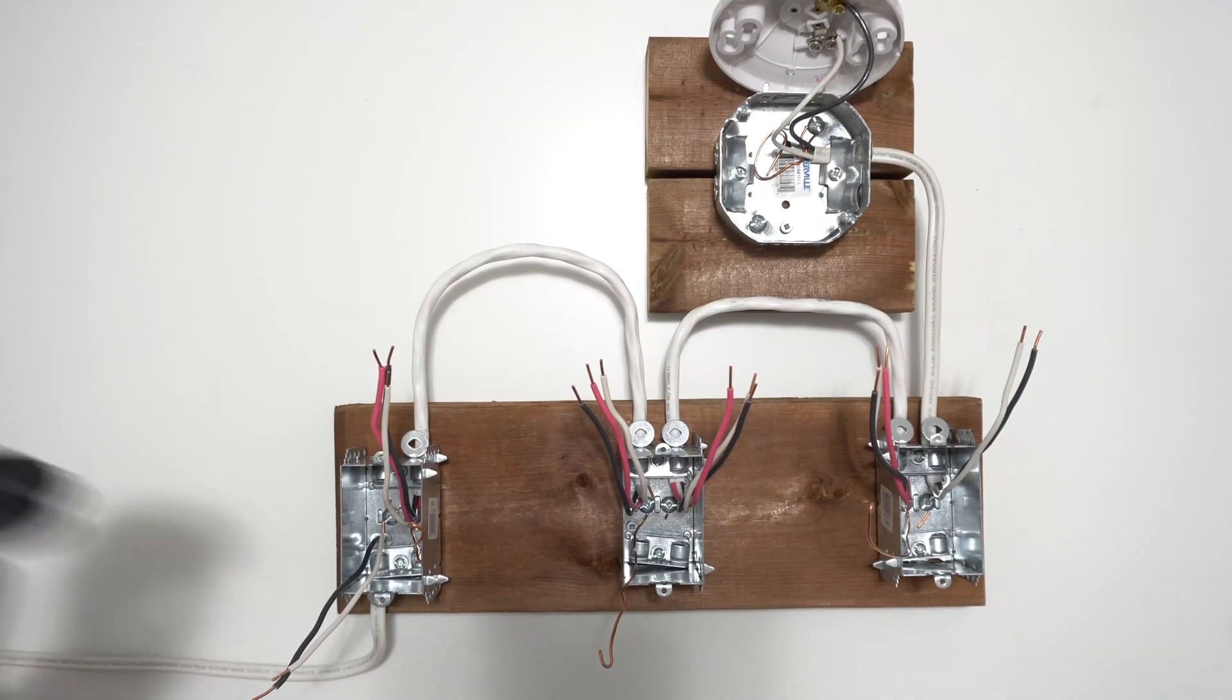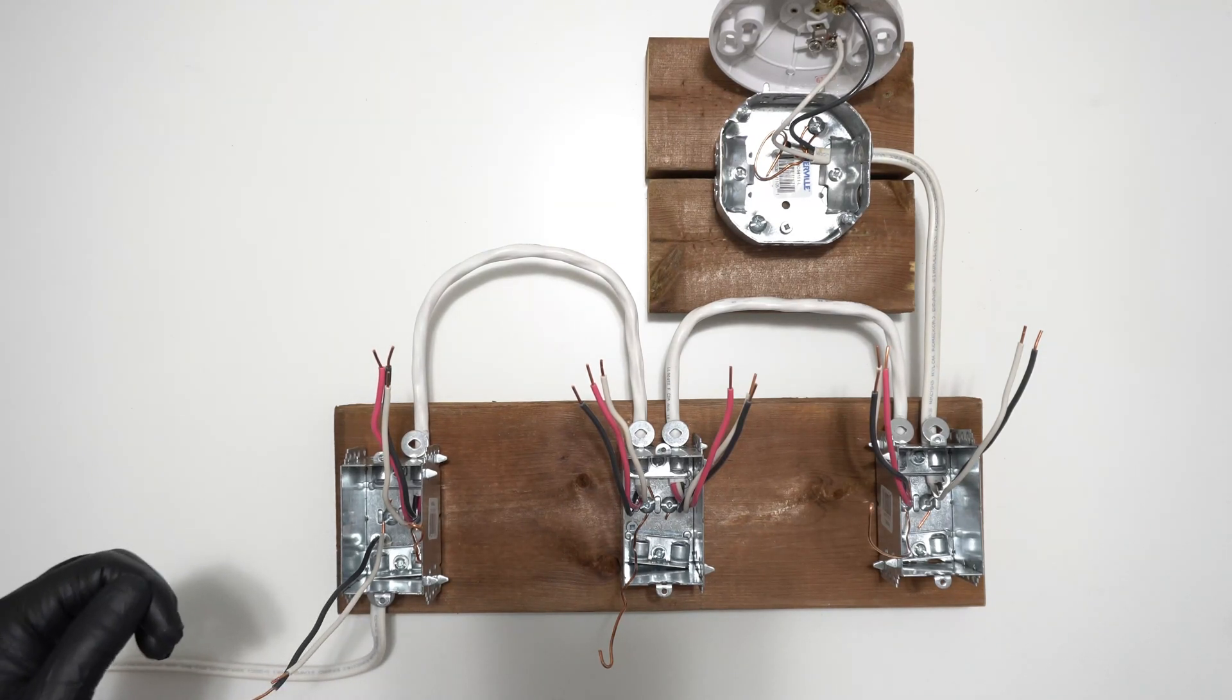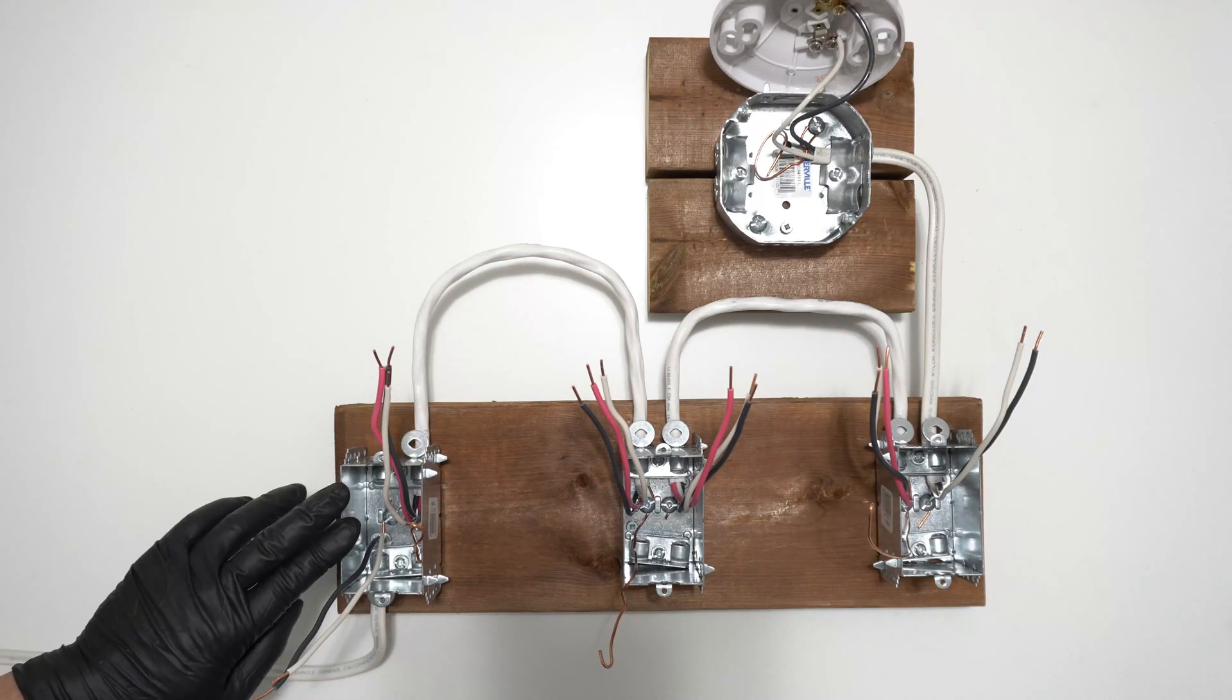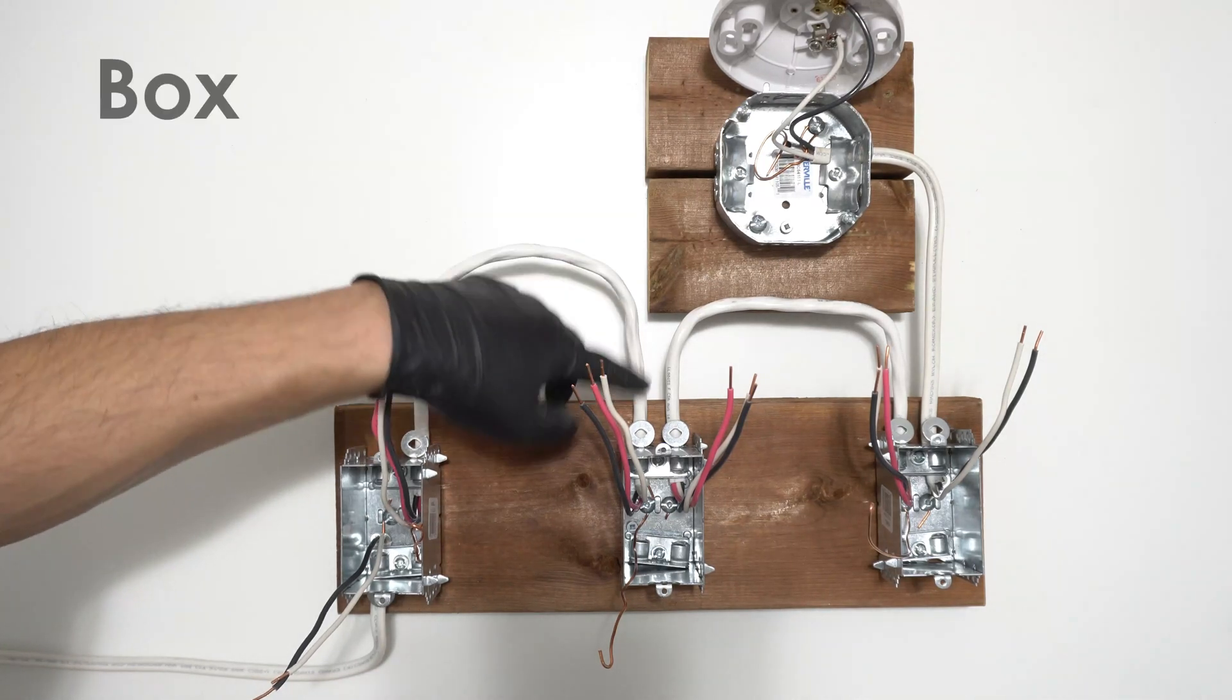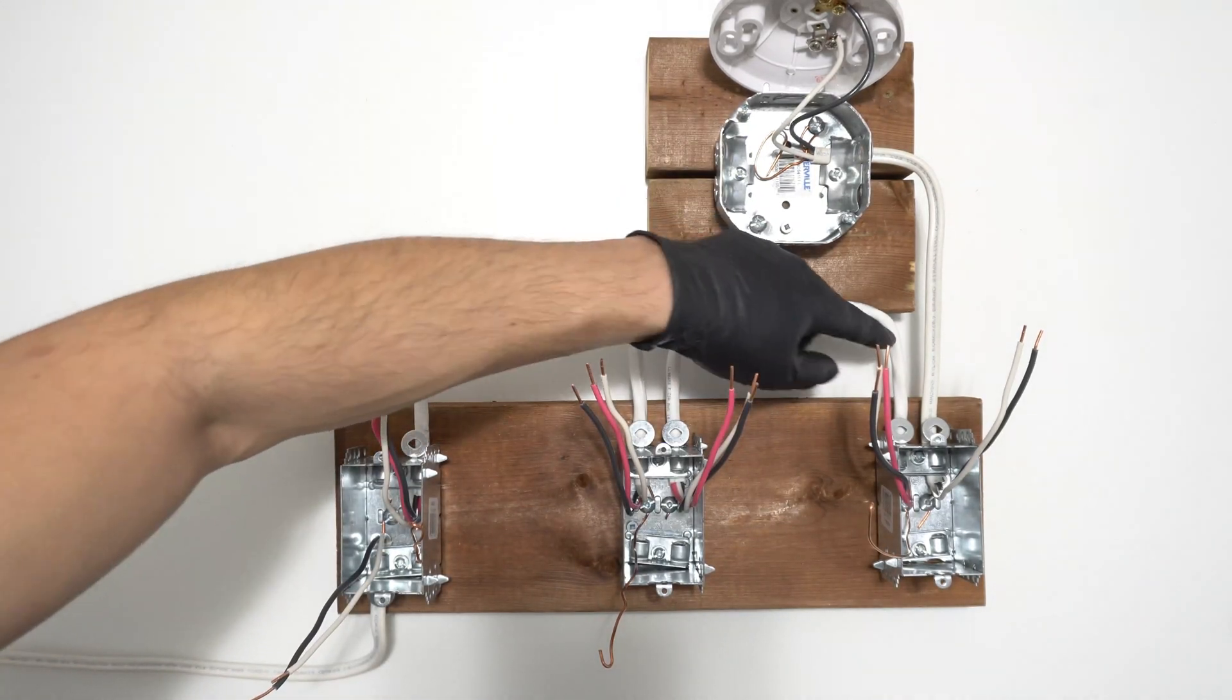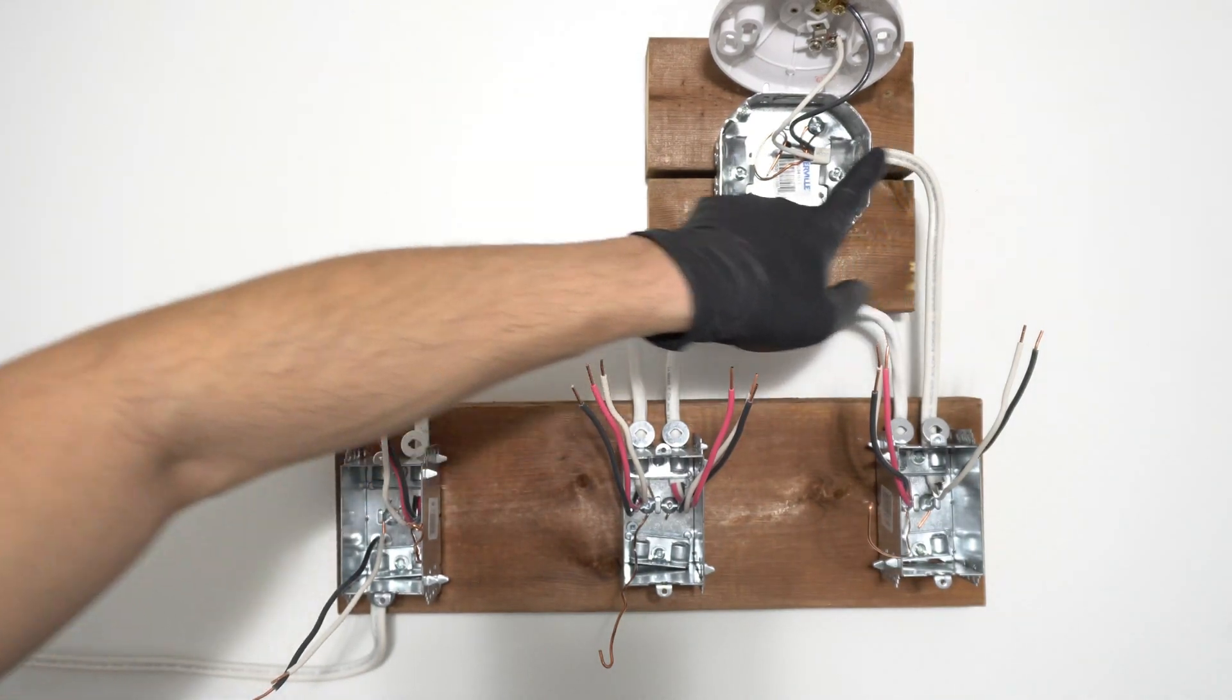In this demonstration we know that this 14-2 is the power source, and if you have drywall the only way to know that this 14-2 is the power source is by using a voltmeter to find a potential difference. The other 14-2 will be coming from the light fixture. Coming out of box A we have a 14-3 wire going into box B, and coming out of box B we have a 14-3 wire going to box C location. Coming out of box C we have a 14-2 going to the light fixture.